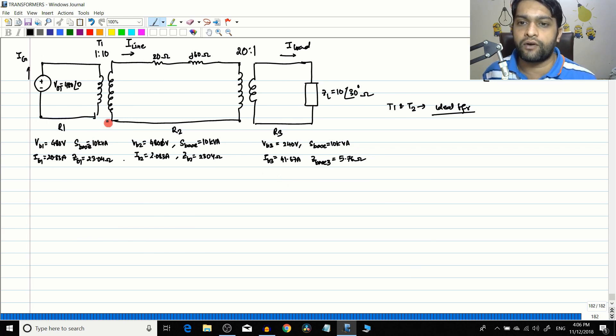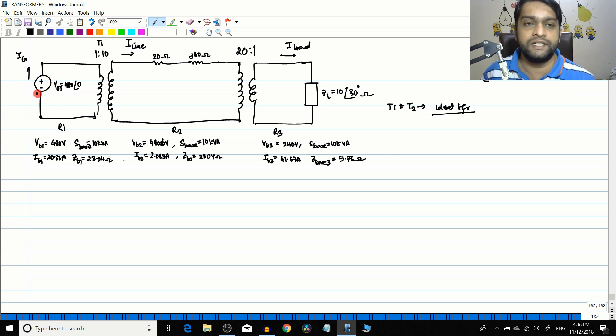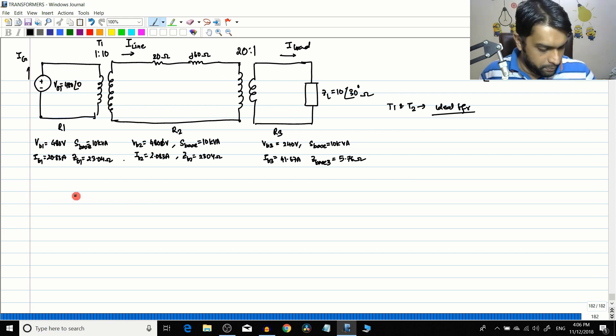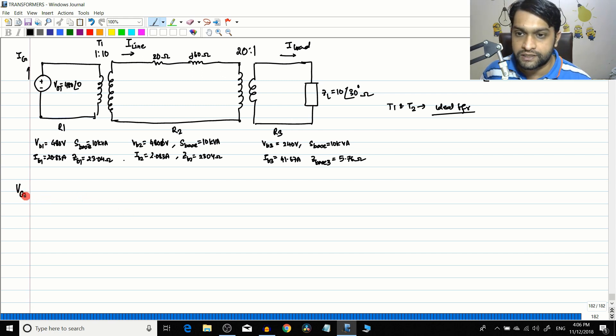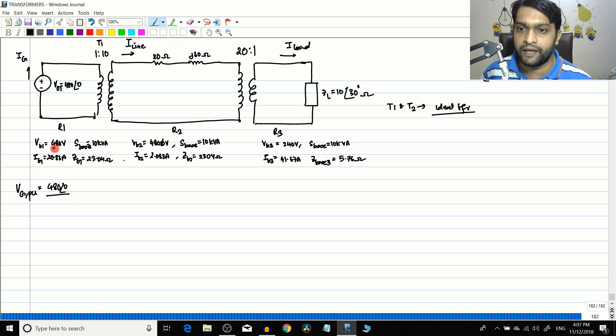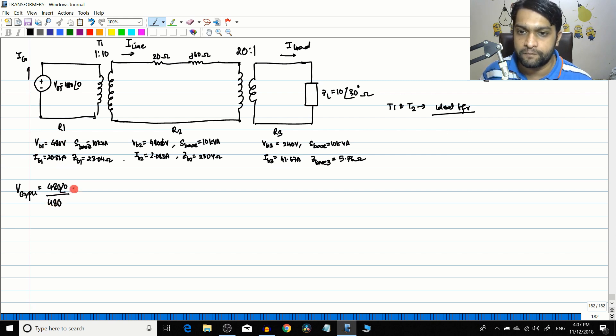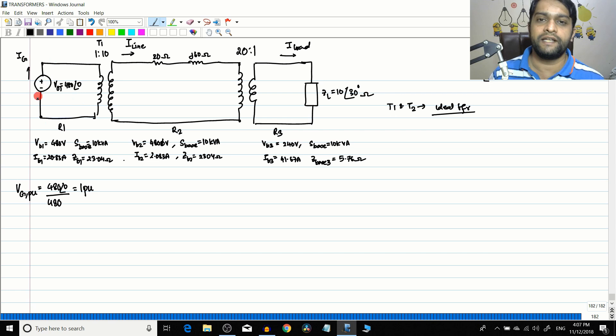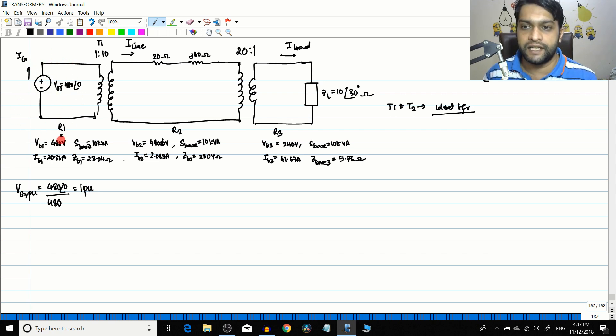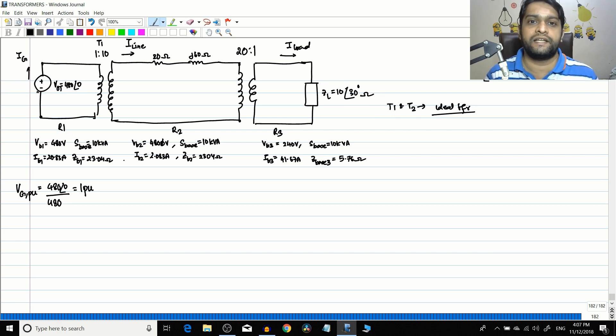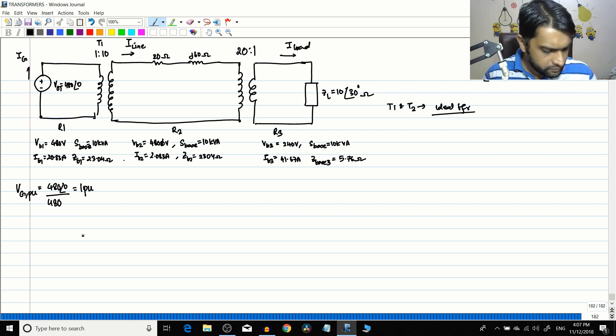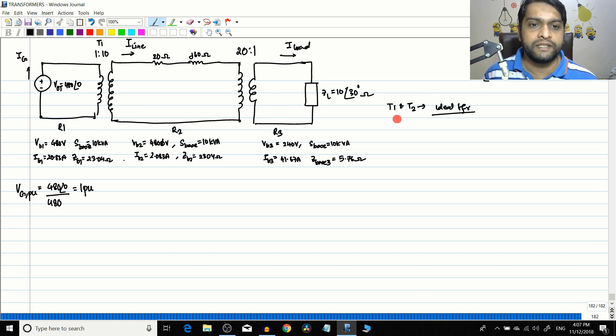Let us start by finding the per unit equivalent for all parameters. On the generator side, Vg is the actual value of the generator. So V_generator_pu equals the actual value 480∠0 divided by the base value V_base, which is also 480. This gives 1 pu. This makes sense because when you select the generator rating as the base value, the generator voltage per unit will always be 1, since the actual value and base value are the same.